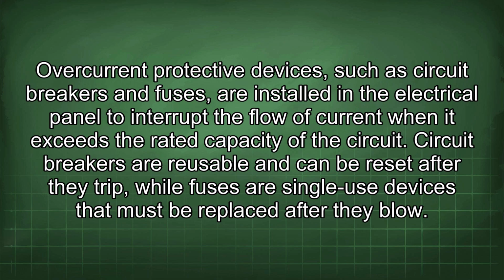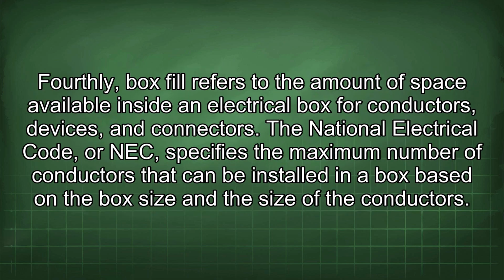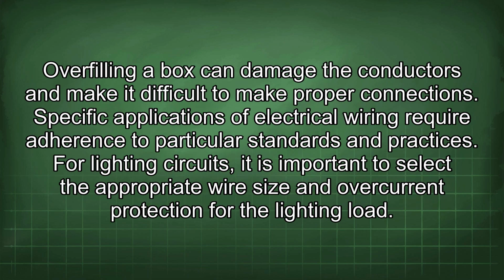after they blow. Fourthly, box fill refers to the amount of space available inside an electrical box for conductors, devices, and connectors. The National Electrical Code, or NEC, specifies the maximum number of conductors that can be installed in a box based on the box size and the size of the conductors. Overfilling a box can damage the conductors and make it difficult to make proper connections.